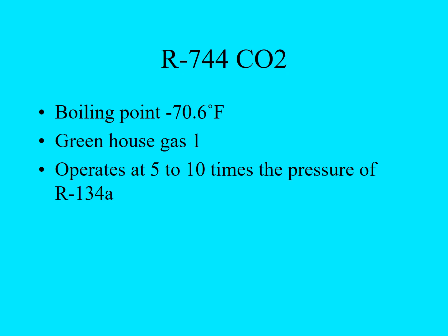The other refrigerant that's being looked at very closely by the European group is using just CO2. Now, CO2 is a gas, so it has a very low boiling point of minus 70.6 degrees Fahrenheit. It wants to be a gas. So just because of that, the greenhouse gas effect is 1. That's our standard. But the operating pressure for a refrigeration system using CO2 is 5 to 10 times the pressure of 134A or 1234YF.